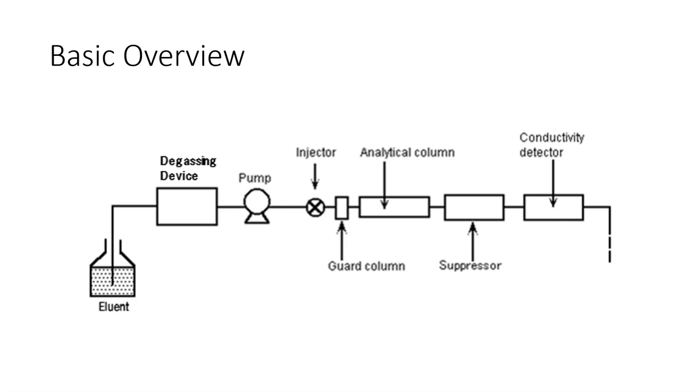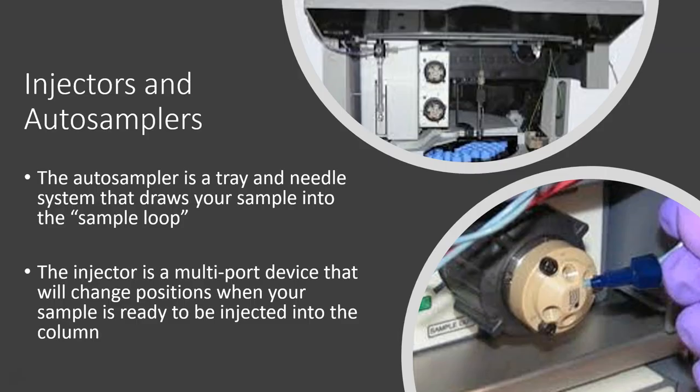Then it makes its way to the columns, but somewhere in here we need to get our sample into the column. So let's talk about how that works. You usually have an injector and an auto sampler. The auto sampler is a tray and needle system that draws your sample into the sample loop. The sample loop is a coil of tubing that holds your sample until it is ready to be injected into the column.